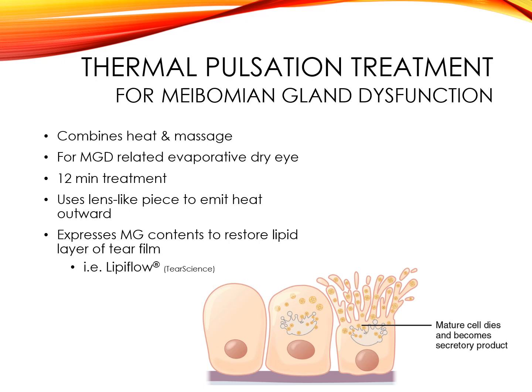Thermal pulsation treatment is specifically aimed at addressing meibomian gland disease-related evaporative dry eye. It combines heat and physical massage to liquefy and express the meibomian gland contents to normalize the lipid layer of the ocular surface. The device consists of a small piece resembling a scleral contact lens, which slides beneath the lids and over the globe. It emits heat outward to the lids while protecting the eye from heat. The second part of the device sits outside the eye on the lids and provides pulsatile squeezing to open gland orifices and express the warmed oil. The treatment takes 12 minutes.